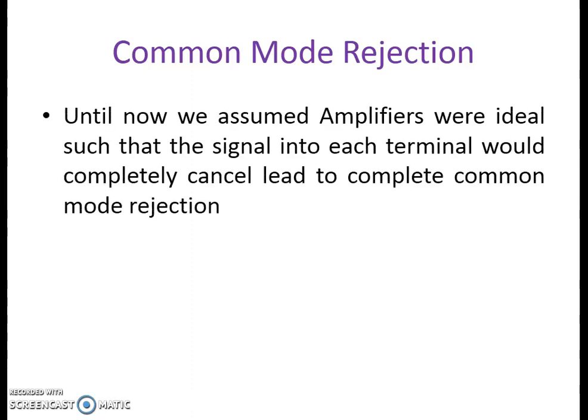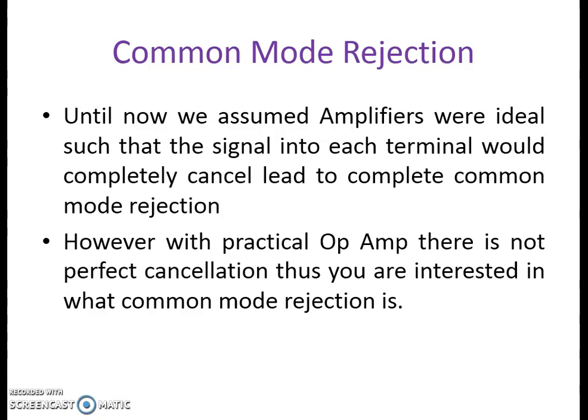Whenever we are designing the preamplifier of the ECG machine, we always have to look for certain noise signals. One of the major sources of noise is the common mode signal. Until now, we have assumed amplifiers were ideal such that the signal into each terminal would completely cancel each other, leading to complete rejection of the common mode signal. But practical op-amps are not ideal — they are incapable of completely canceling the common mode signal which appears at the input terminals.